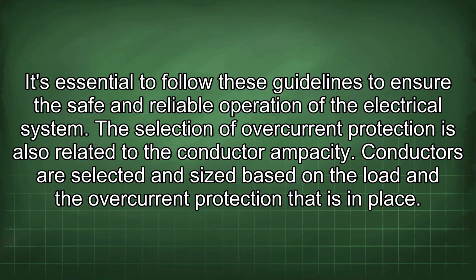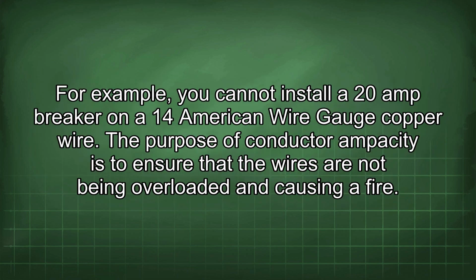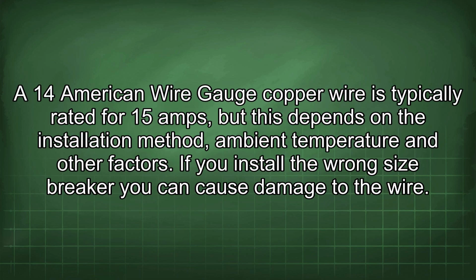The selection of overcurrent protection is also related to the conductor ampacity. Conductors are selected and sized based on the load and the overcurrent protection that is in place. For example, you cannot install a 20 amp breaker on a 14 American wire gauge copper wire. The purpose of conductor ampacity is to ensure that the wires are not being overloaded and causing a fire. A 14 American wire gauge copper wire is typically rated for 15 amps, but this depends on the installation method, ambient temperature and other factors. If you install the wrong size breaker, you can cause damage to the wire.